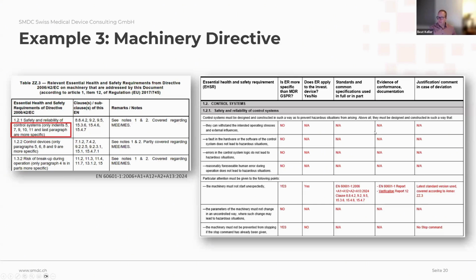What else do we have? Where is the ZZ3 published? The ZZ3 is published in the A13. What is important is that you don't find it in the IEC or ISO version of the standard. This is only in the EN version. And what CEN and CENELEC try is to get it published at the same time as the international version is published. Then we don't need any amendments. If this is not feasible, like it was with the 60601-1, then the Z annexes and the national foreword get published in their own amendments. And these amendments then start with 11, 12, 13, so they have a two-digit number.